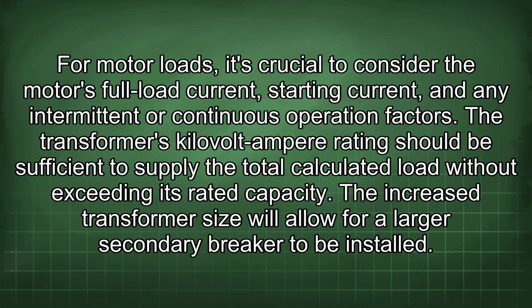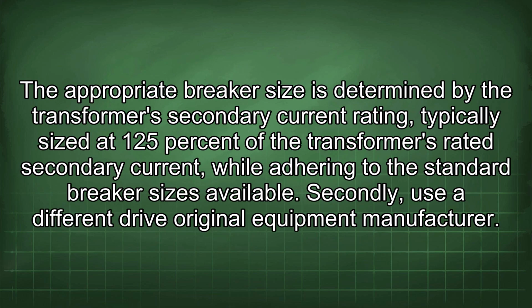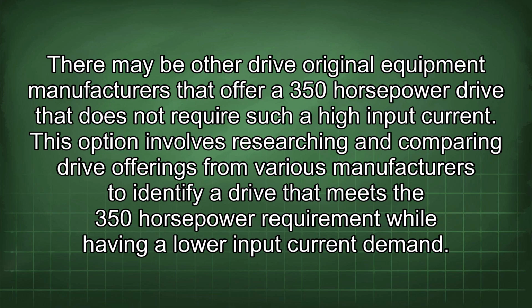The increased transformer size will allow for a larger secondary breaker to be installed. The appropriate breaker size is determined by the transformer's secondary current rating, typically sized at 125% of the transformer's rated secondary current, while adhering to the standard breaker sizes available. Secondly, use a different drive original equipment manufacturer.